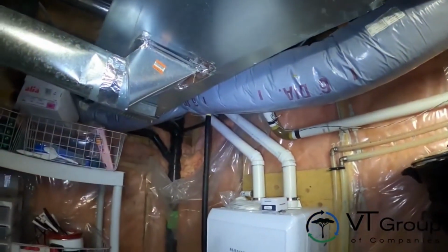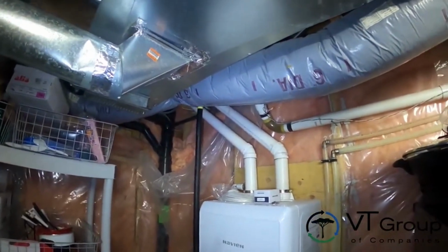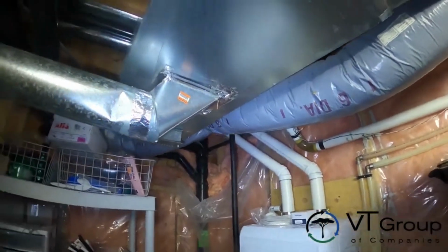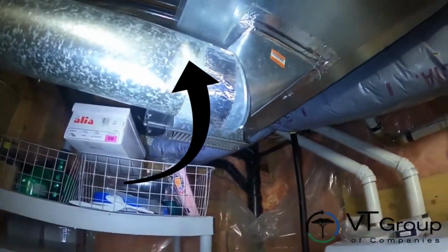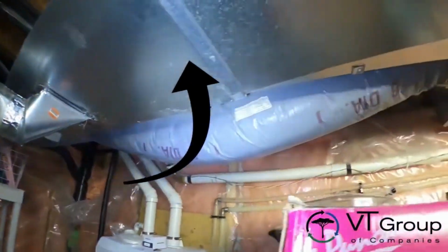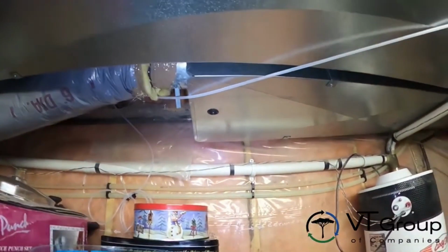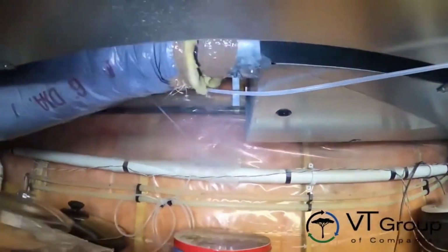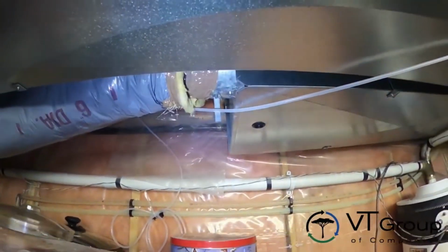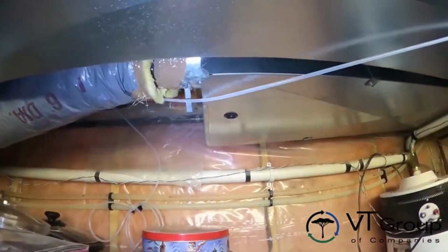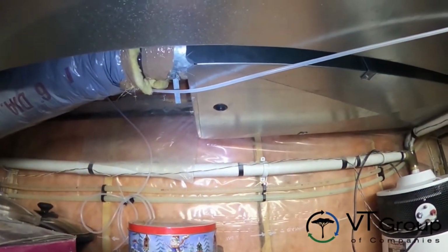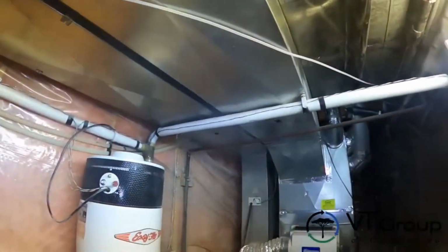Okay, so fresh air intake meaning outside air comes into your home. The other duct adjacent to it, this one here, has a supply air register. That's a supply air, and this comes into the return air side of the ductwork. Because it's on the return air, there's a negative pressure in the ductwork, and therefore this will be bringing outside air in because that duct where it goes into is in the negative pressure. But let's have a quick look at the furnace itself.